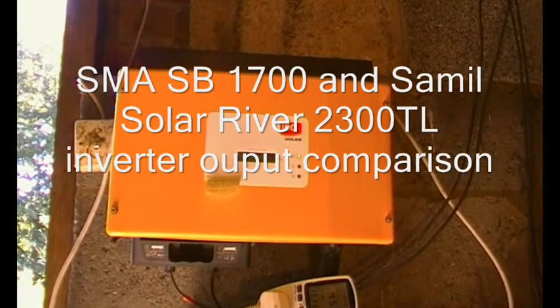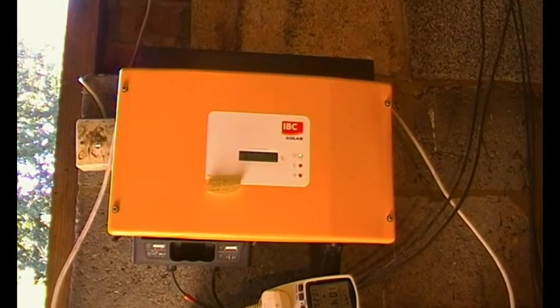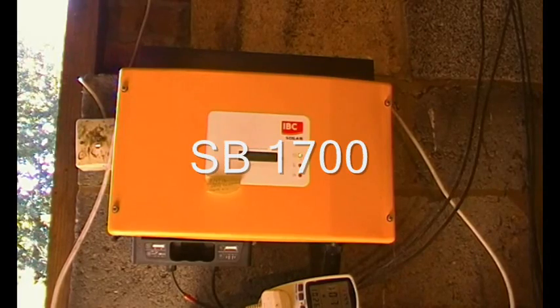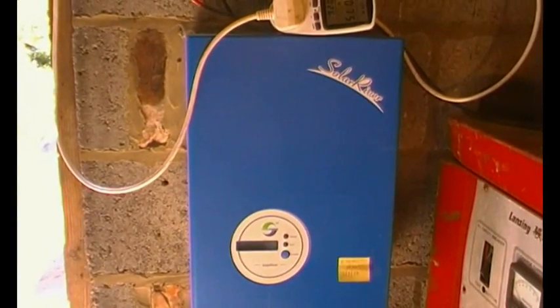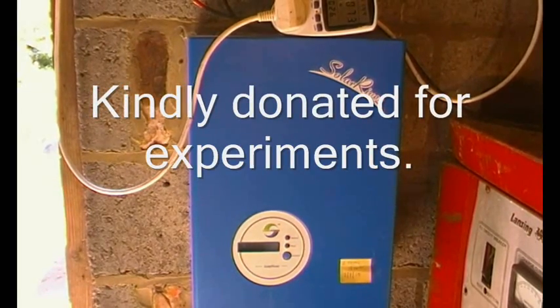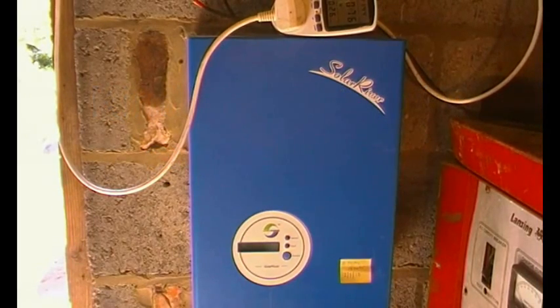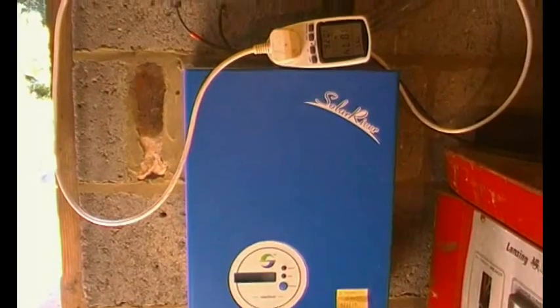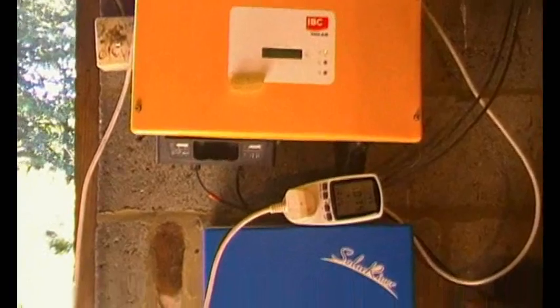This is a comparison video between a transformer-based SMA SB1700 grid tie inverter and a non-transformer, more modern Solar River grid tie inverter. The Solar River is G83/2 certified, and one interesting thing is that it fires up really quite quickly — about 30 seconds — whereas the SMA takes quite a while. We've also got an energy monitor here.